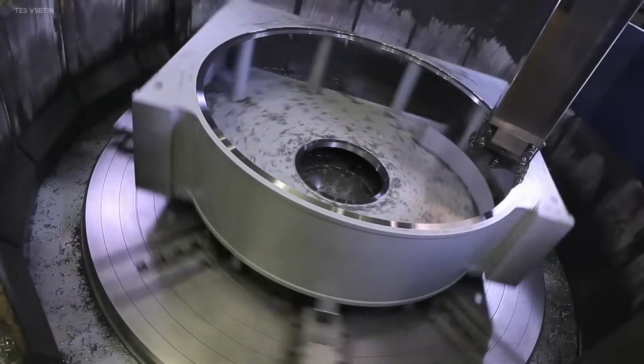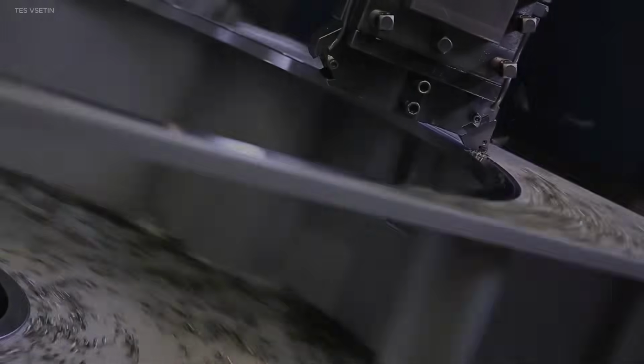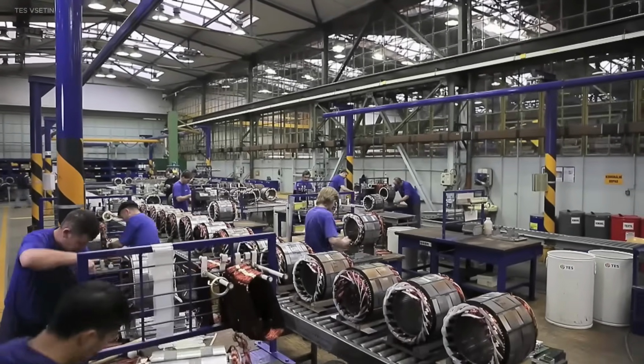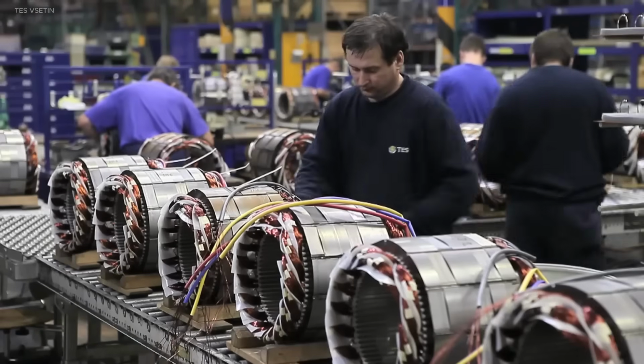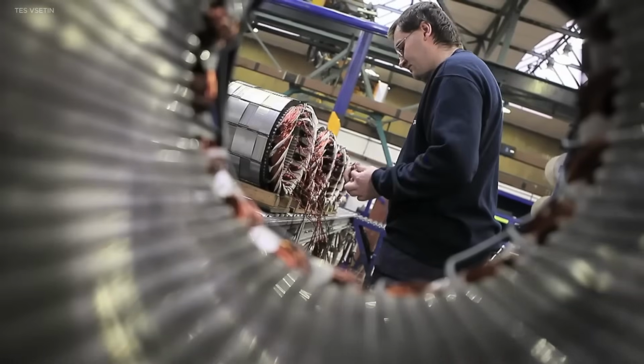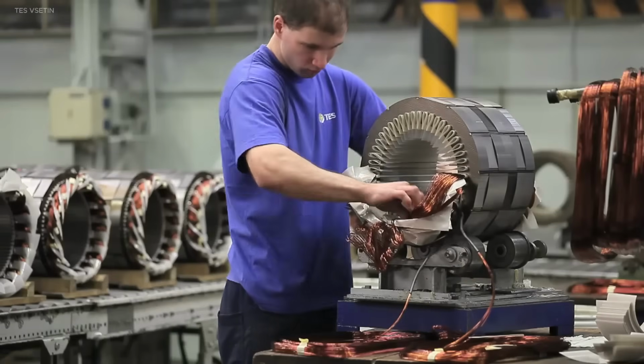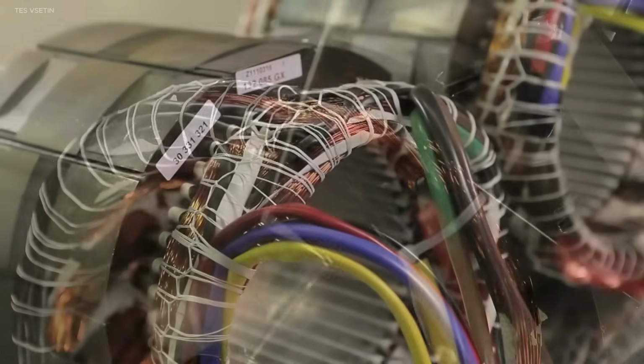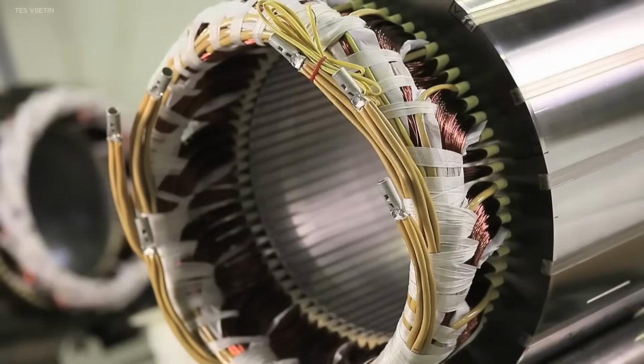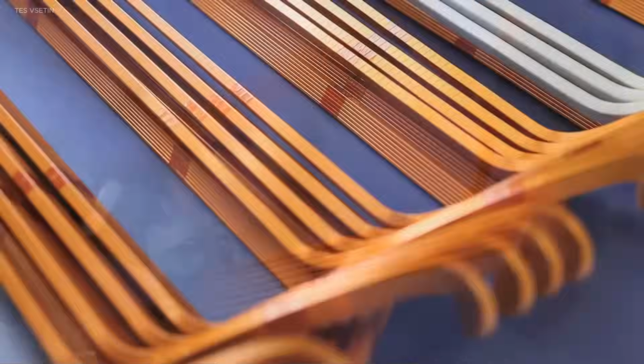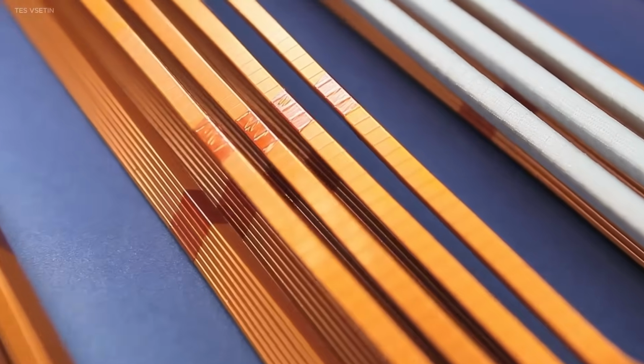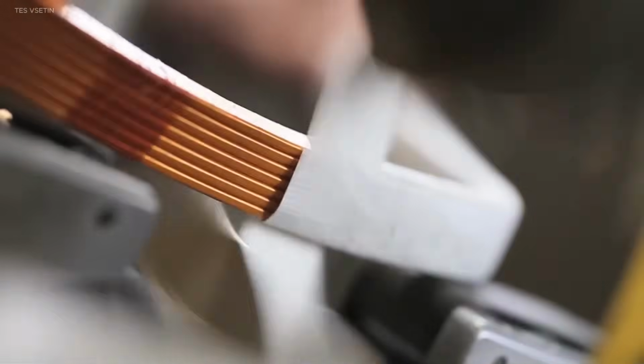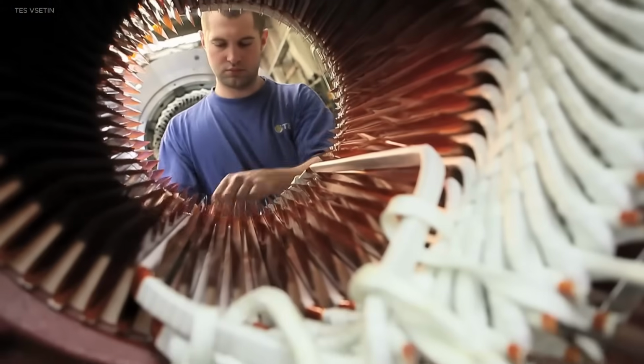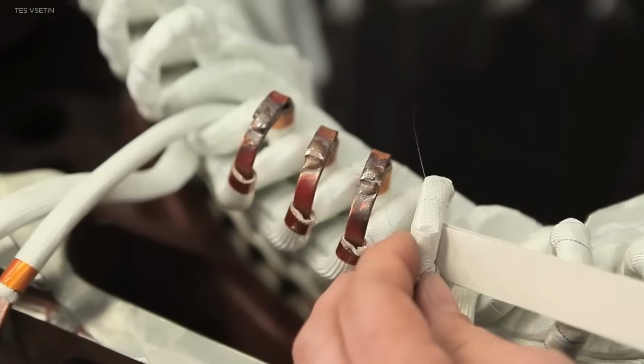Next, the winding and assembly stage involves inserting coils, performing electrical connections, and impregnating the windings with resin to enhance insulation and mechanical strength. Final assembly integrates all components into a complete machine. Each generator is tested in the test field using advanced equipment to verify electrical performance, mechanical balance, and noise levels. Results are documented for quality assurance and certification compliance.